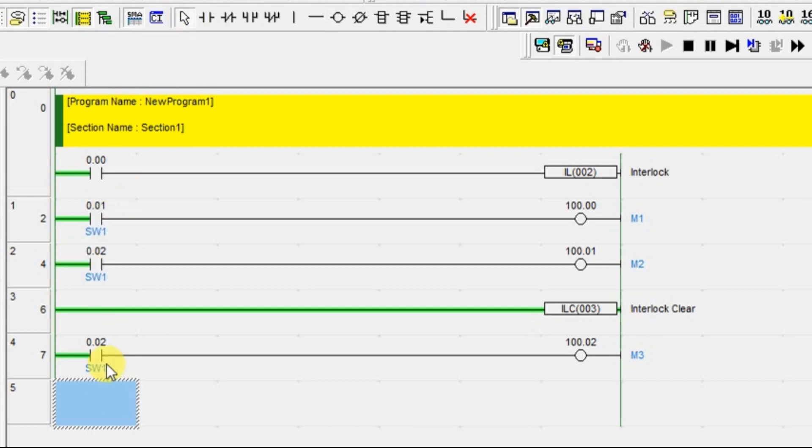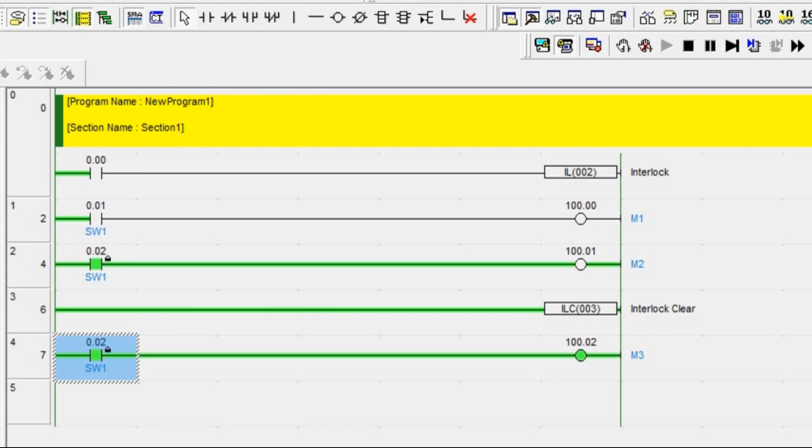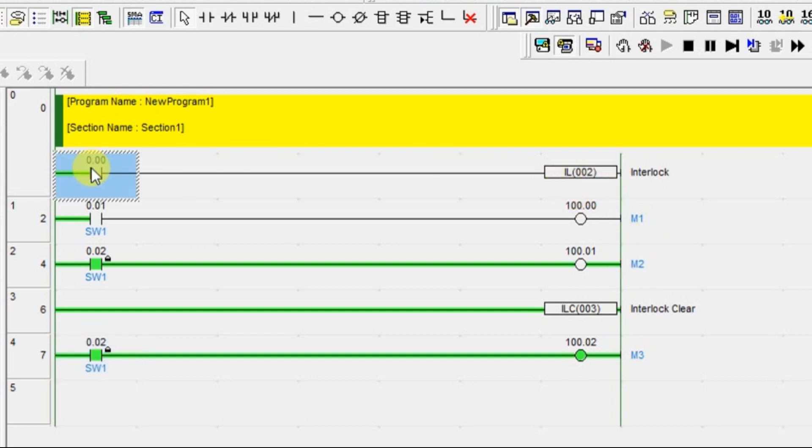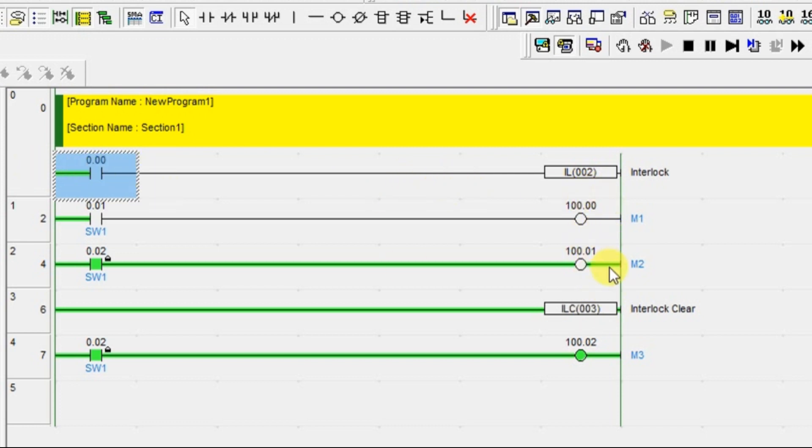Now turn on this and your motor 3 is running. But, for the same input your motor 2 is not running. Why? Because the interlock area is off. The condition 0.00, I have given as an interlock input. Since it is off, you could not be able to perform these two outputs.